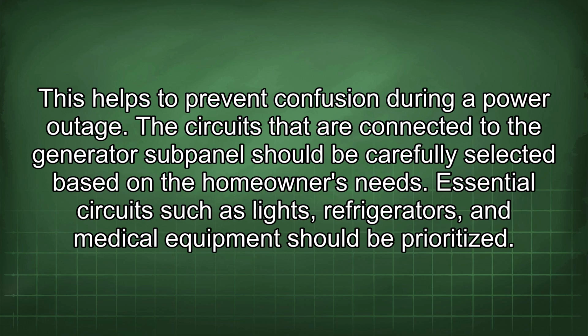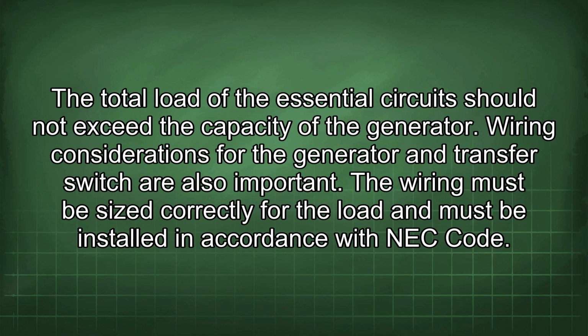The circuits that are connected to the generator subpanel should be carefully selected based on the homeowner's needs. Essential circuits such as lights, refrigerators, and medical equipment should be prioritized. The total load of the essential circuits should not exceed the capacity of the generator.